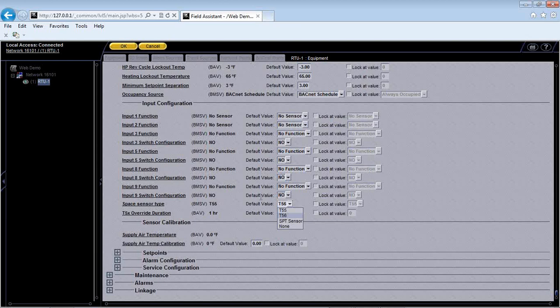Okay? So once I've got that, this box here is if you have a T55 or T56, those sensors come standard with a little button for manual override on it. If you click that button, it will go into override for this 1 hour. So you can actually tell it how long you want the override duration to be. So if I want to give them 3 hours, I would just type in 3 here, then I have 3 hours of override time, non-occupied time switching to occupied.